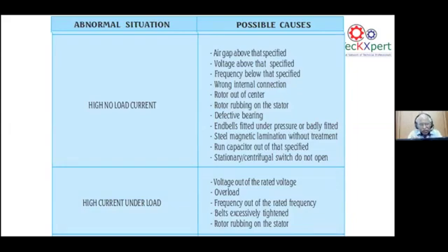So these are the areas in the motors where high no load current is happening, and the areas where this can be controlled. These are all the possible causes, and it is not only on the high current but on underload also. It is happening due to load, and due to the motor condition. Both aspects we can analyze and see to it that the motor is kept in the normal loading range, with excellent protection on the overload and prompting protection on the underload as well.